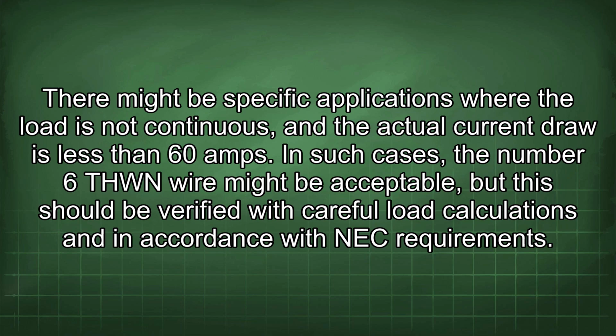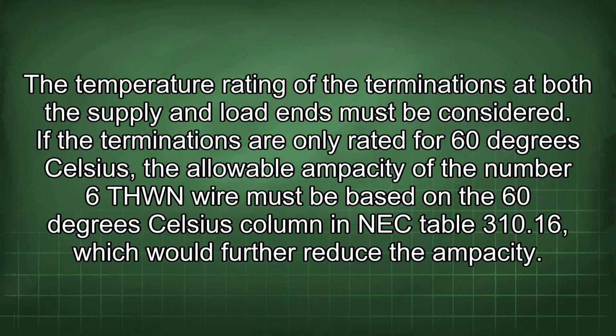There might be specific applications where the load is not continuous and the actual current draw is less than 60 amps. In such cases, the number 6 THWN might be acceptable, but this should be verified with careful load calculations and in accordance with NEC requirements. Temperature rating of the terminations at both the supply and load ends must be considered.